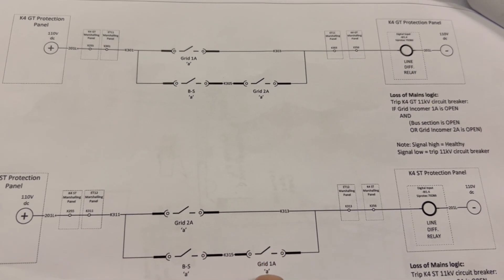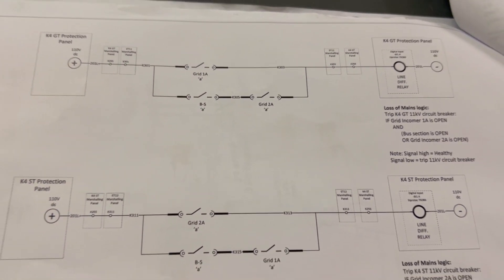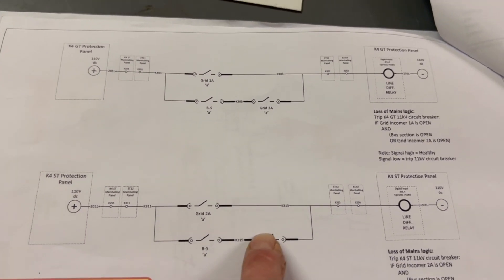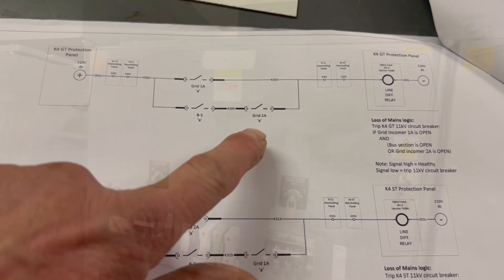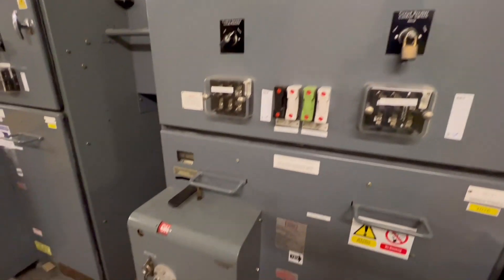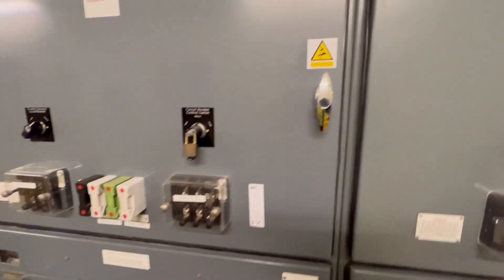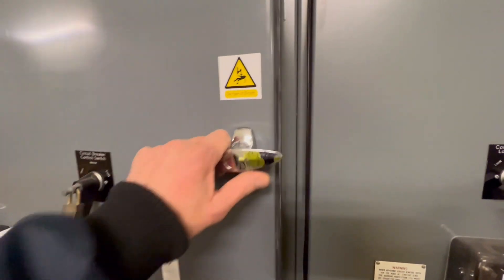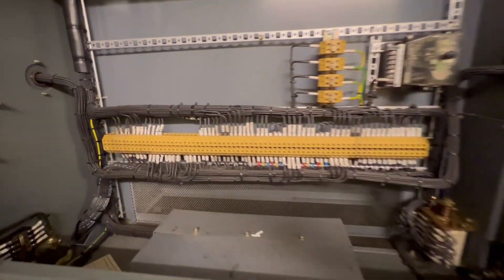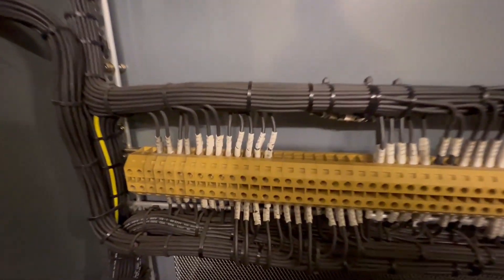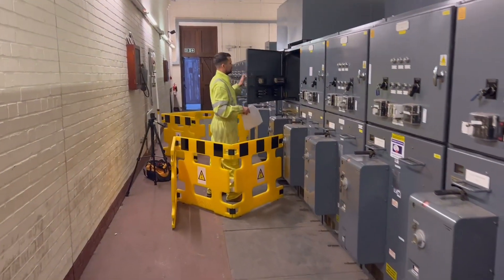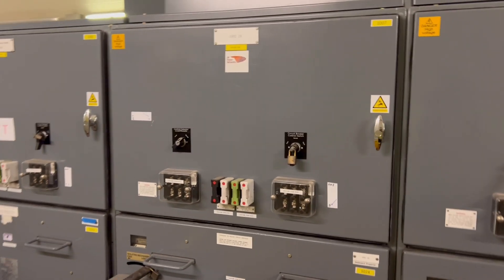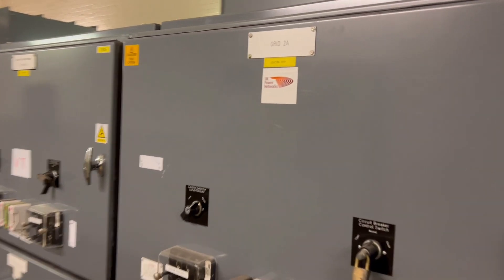Auxiliary contacts on the three associated circuit breakers for Grid 1A, 2A, and the bus coupler need to be tested to ensure they are operating correctly. The wiring has already been checked between the units to make sure the correct signals can be generated, but we now have to physically open each of the associated circuit breakers to check that the auxiliary contacts are working correctly. The connections for these auxiliary contacts are at the front of the panels and had to be disconnected in turn and checked during breaker operation.